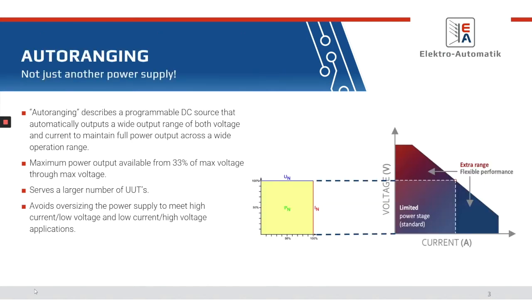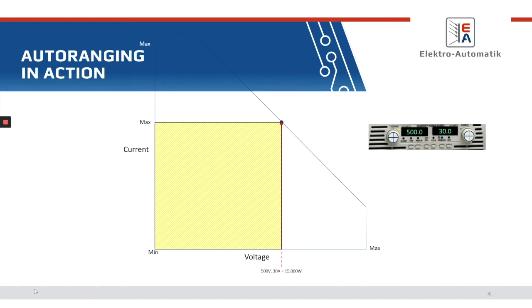So let's take a look at auto-ranging, kind of the theory of operation. Auto-ranging is just a term, and it basically describes the power supply's ability to automatically adjust its output level from a current perspective to maintain that full power output across a larger operating envelope. What you'll see in the yellow is what we call a traditional standard square operating curve power supply. And to the right, you'll see where the extra range fits into this. The result is that you end up with a full power output across a very large range. The power supply can test a lot of different products, and you don't really need to oversize that power supply with an auto-ranging power supply to the extent that you would with a square operating curve. So let's go ahead and take a look at some specific examples.